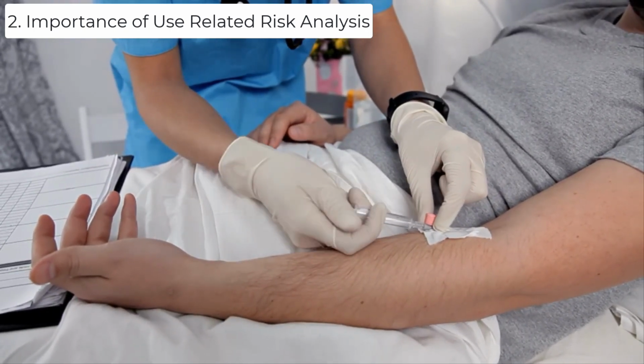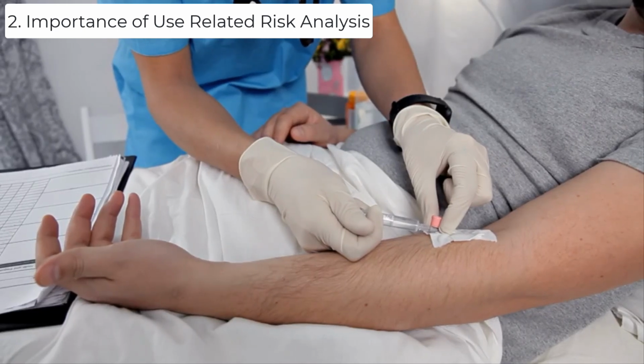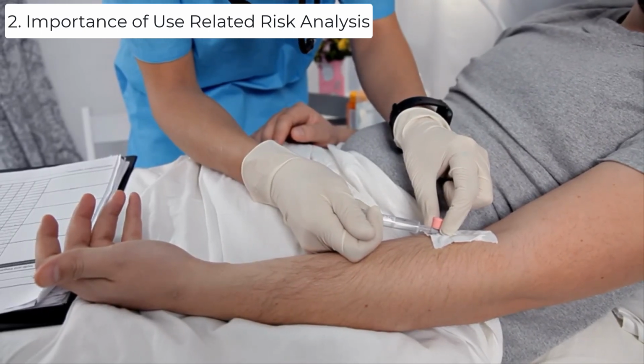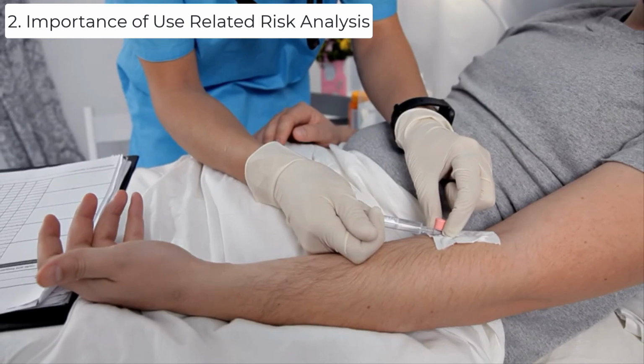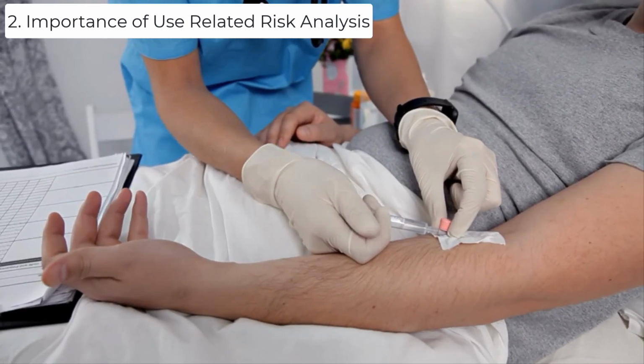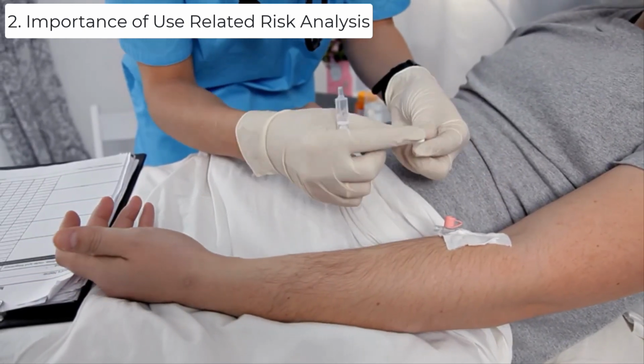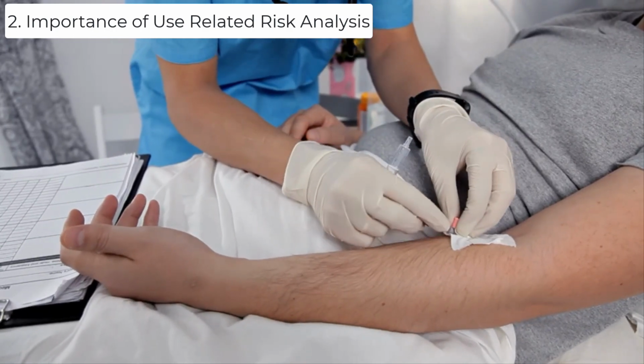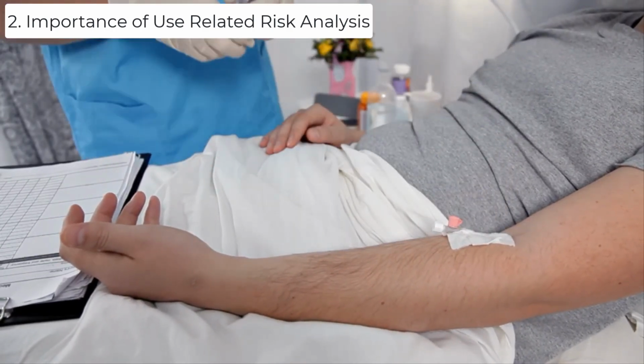This document makes clear that the FDA may request the use-related risk analysis if there's any safety concern at all. If the use-related risk analysis shows any unacceptable risks, a human factors validation study might be required, and a draft of the study protocol should be submitted for feedback before proceeding.